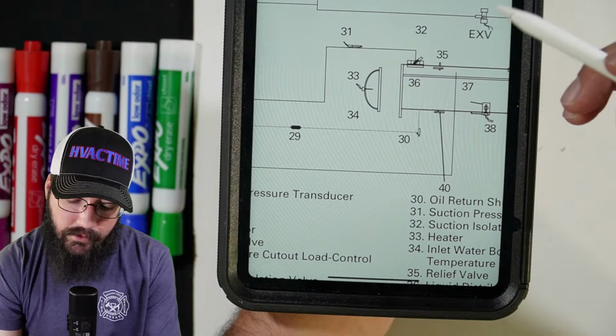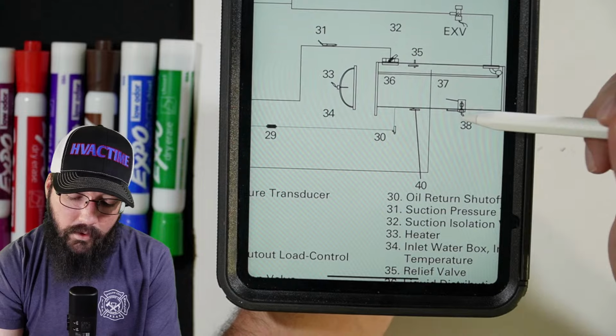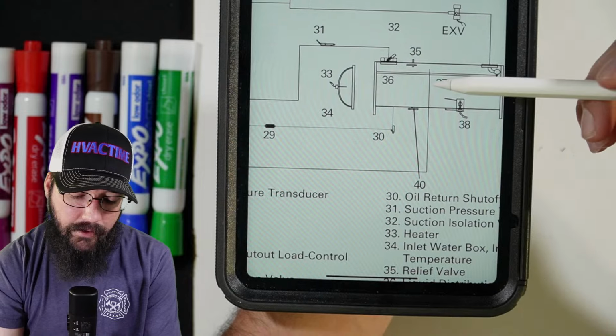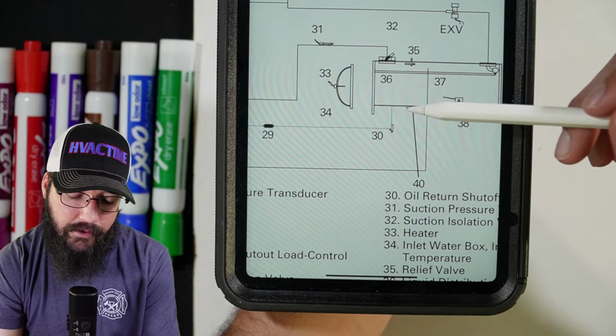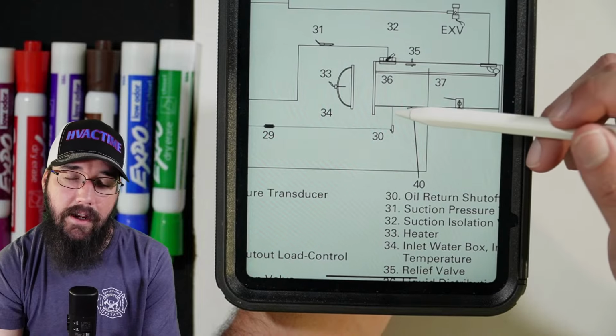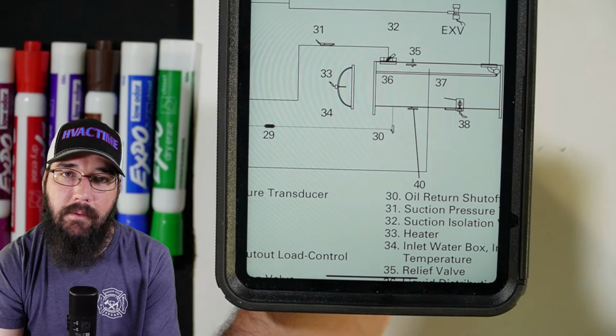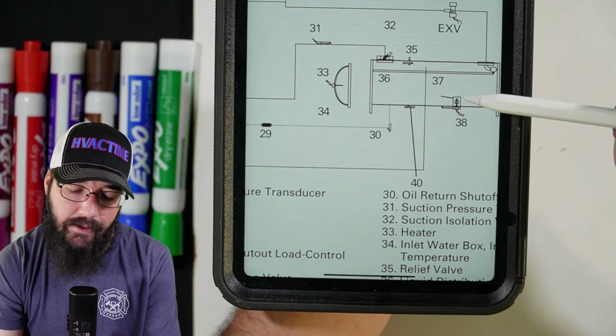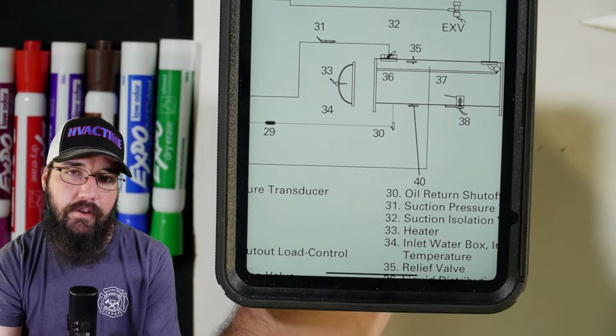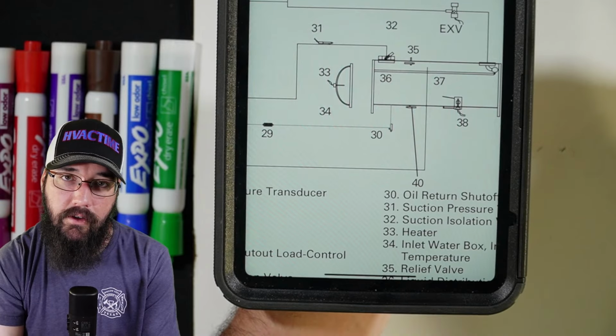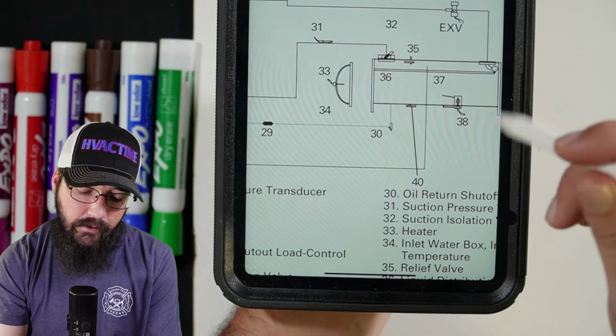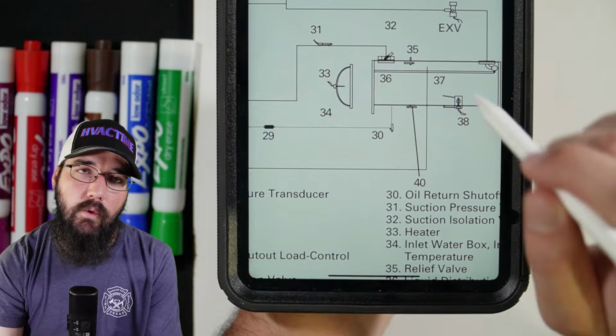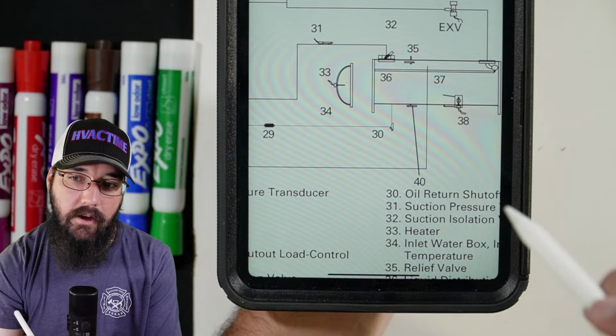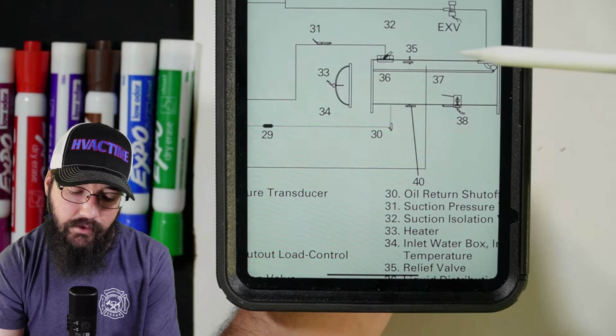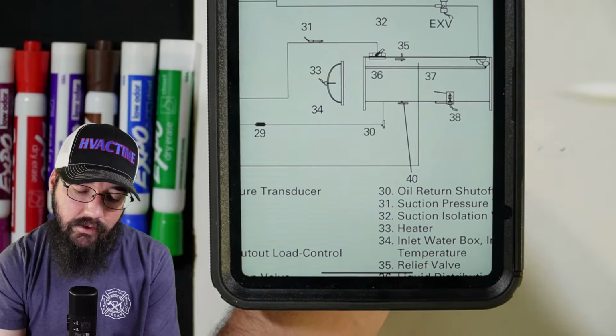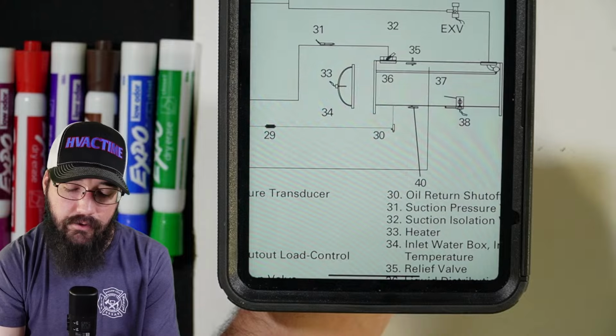And it's a pain in the butt to try to work around. So whether you try to fool the sensor to increase the liquid level enough to start getting some of that oil to return, we just have to try to do something to keep the machine online and get that oil back. That becomes the tricky part, because part of what will happen is it'll read high level, it'll start to starve the evaporator, that'll turn into suction limiting if it doesn't just go into full-on suction pressure trip. A whole series of that oil in the evaporator could cause several reactions that are shown as symptoms in other ways, like suction pressure limiting being one of them, because it is starving the evaporator. Not even a heat exchange issue.